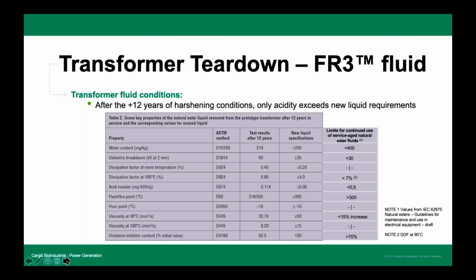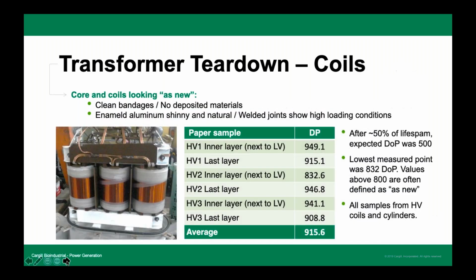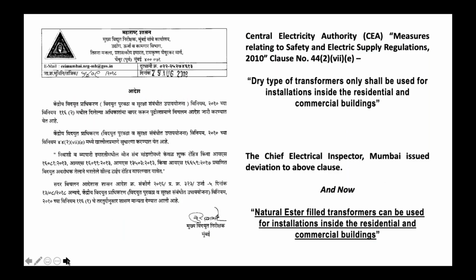That brings us to the conclusion. This is what I spoke about. If you can see this slide correctly, the aging of the transformer can only be seen at the weld joints where copper to copper is welded. There you find it is slightly blackened and the aging is there. Otherwise, it's as good as brand new. Let's move on. Next slide, please.